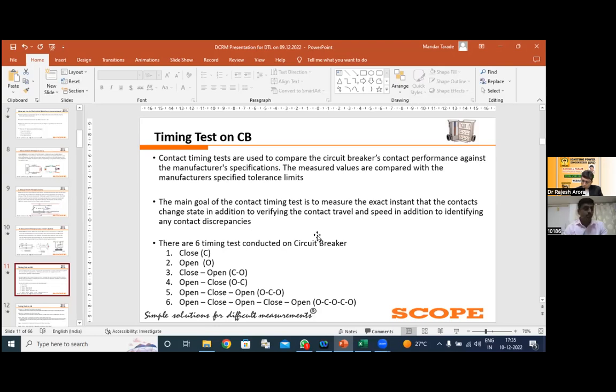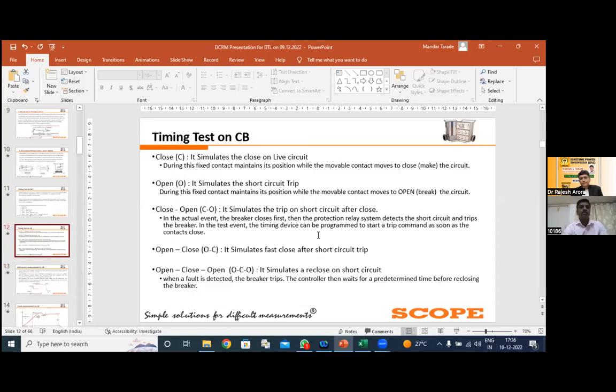According to the IEC standard 62271-100, we are performing different timing tests on the CB. Likewise, the first one is the close, the second one is the open, the third one is the CO, that is close-open, then the OC, open-close. OCO is basically used to check the auto reclosure mechanism. That is for the single-shot auto reclosure mechanism. And if you are having the multi-shot auto reclosure mechanism, then we are performing the OCOCO test, where we are performing the test O, 300 millisecond, CO, then 3 minutes, CO. And accordingly, we are checking the health of the contact timing, or the health of the timing.